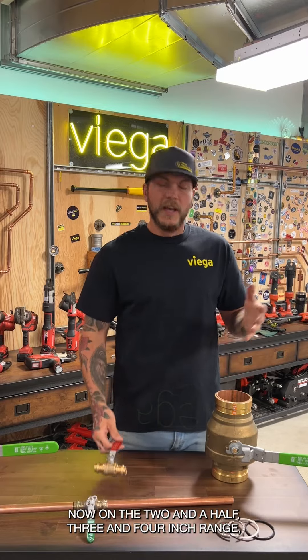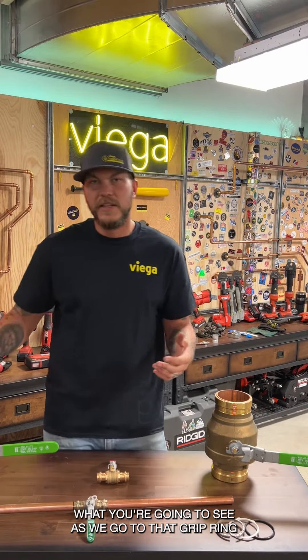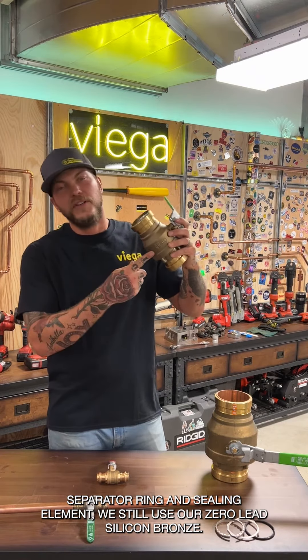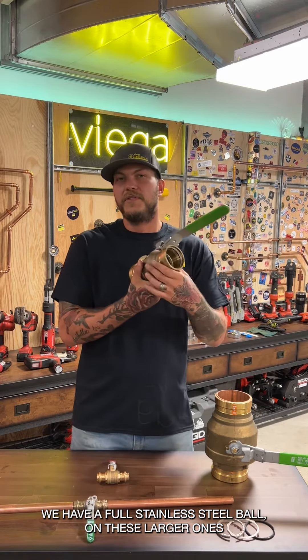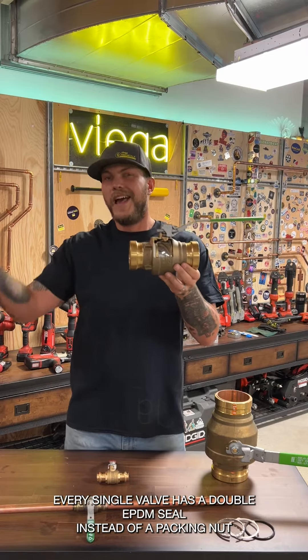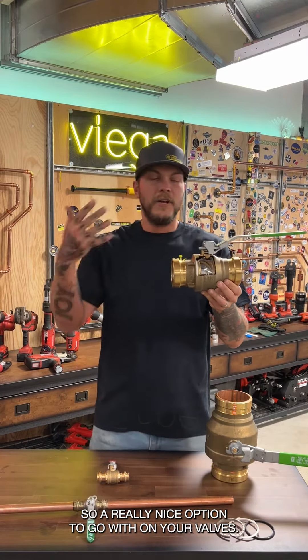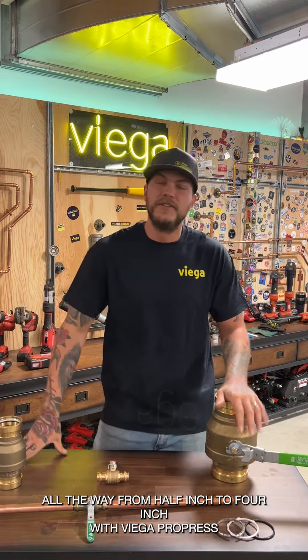In the two-and-a-half, three, and four inch range, we move to the grip ring, separator ring, and sealing element, but still use zero lead silicon bronze. The difference is that the smaller valves have a full stainless steel ball, while these larger ones are chromium plated. Every valve has a double EPDM seal instead of a packing nut, from half inch to four inch with Viega ProPress.